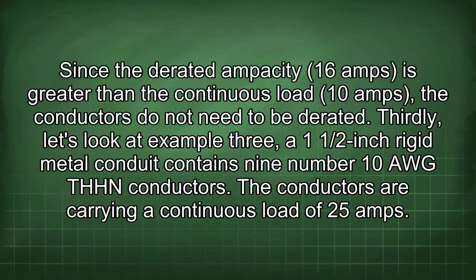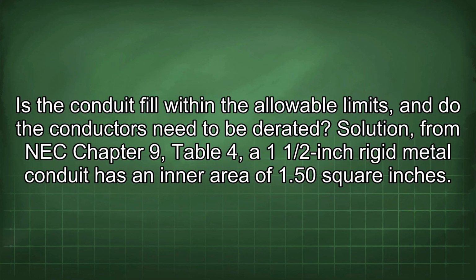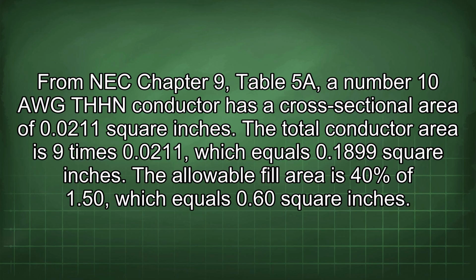A 1 1/2-inch rigid metal conduit contains 9 number 10 AWG THHN conductors. The conductors are carrying a continuous load of 25 amps. Is the conduit fill within the allowable limits, and do the conductors need to be derated? Solution from NEC Chapter 9, Table 4. A 1 1/2-inch rigid metal conduit has an inner area of 1.50 square inches. From NEC Chapter 9, Table 5a, a number 10 AWG THHN conductor has a cross-sectional area of 0.0211 square inches.